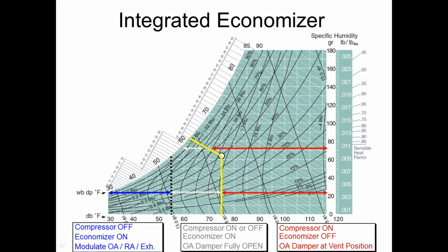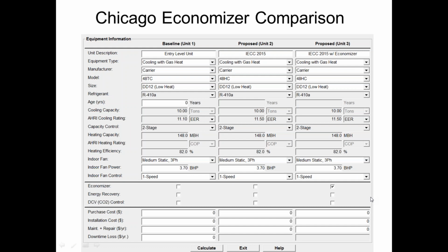By the way, to do an integrated economizer, you have to have a 2-stage thermostat. The Y2 command off of the thermostat, the second stage command, is what actually energizes the compressor. If you have a 1-stage thermostat, regardless of how awesome your rooftop or your economizer are, you're not going to get integrated economizer. The thermostat on the wall has to be a 2-stage stat, even on a 1-stage compression unit. So just keep that in mind as we go through.